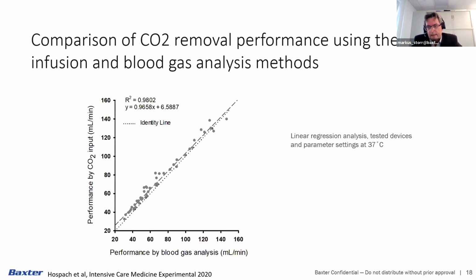I mentioned the CO2 removal performance was analyzed using this quite simple infusion method, which is based on the measured amount of CO2 we infused into the closed test circuit. Using blood gas analysis, we've checked the validity of this simple method, as you can see here from this linear regression analysis, which compared the two methods. The two methods yielded very similar results, which shows the validity of this quite simple test method for CO2 removal.